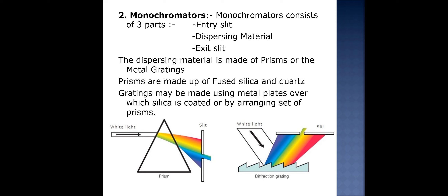The second instrument is the dispersing material, also known as the monochromator. The monochromator consists of three parts: the entrance slit, through which polychromatic light enters; the dispersing material, where the polychromatic light disperses into its single components; and the exit slit, from which the monochromatic light at the required wavelength exits and passes on to the sample. The dispersing material is made up of prisms or metal gratings. Prisms are made of fused silica and quartz — glass is not used because it absorbs UV radiation. Gratings may use metal plates coated with silica or an arrangement of prisms.